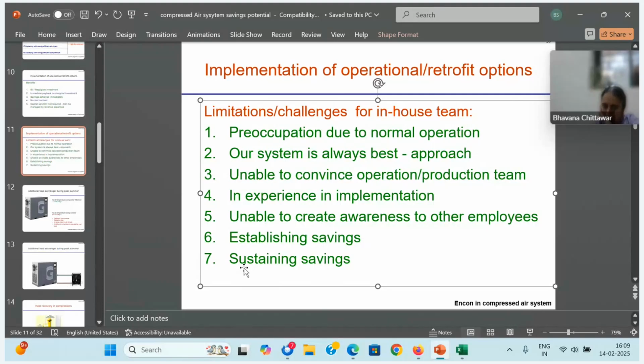Yes. And sir, the second question, just finishing my query. This VFD operated compressor, you told that they may have locked the speed. What we would suggest in some cases, even though the client has installed a VFD to optimize the loading and get the savings, they are not getting the savings. Sometimes the unloading occurs and power is consumed in the unloading region. So should we recommend they change the speed settings, so that unloading will not occur?